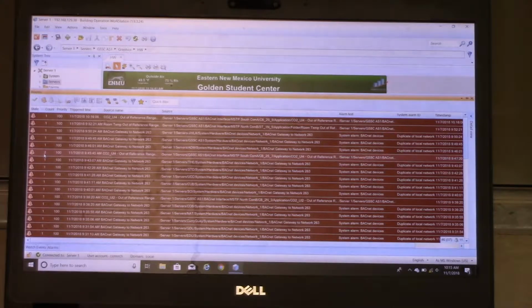Maybe we're telling it to start, it doesn't start, so we go into alarm, and then we tell it to turn off. So then it's already off, so there's no problem anymore, so the alarm clears. So you might have a scenario where you're calling for a fan and it's just not coming on.